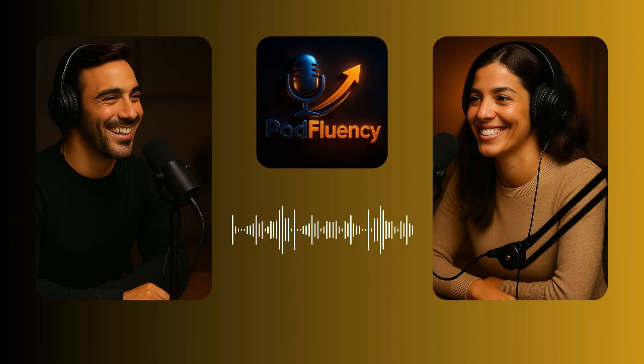And speaking of series capacitors, I see the sources mention those briefly as well. How are those different? Series capacitor banks are actually installed in series with the transmission lines themselves, rather than within the substation. They help to reduce voltage drops and increase the power transfer capacity of the lines, which can be especially beneficial for long transmission lines. Interesting. So they're like adding a booster pump to the water pipe to help it flow more easily.